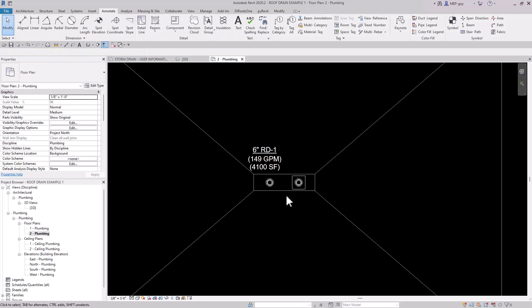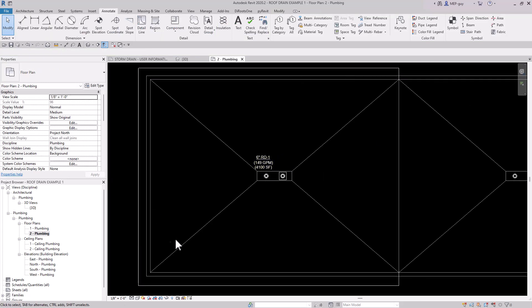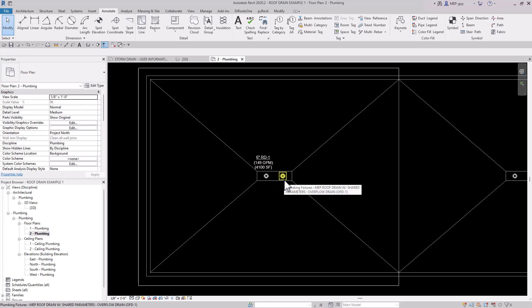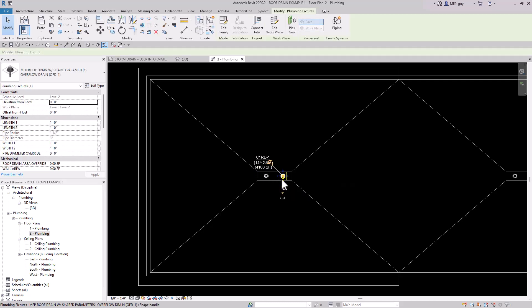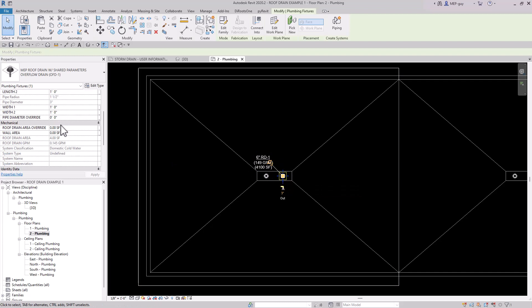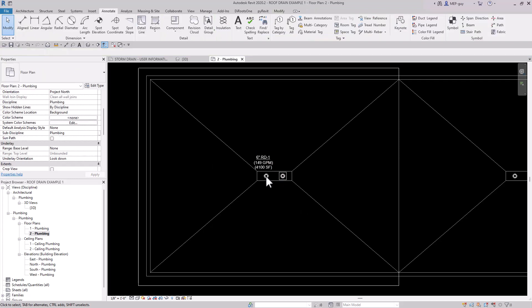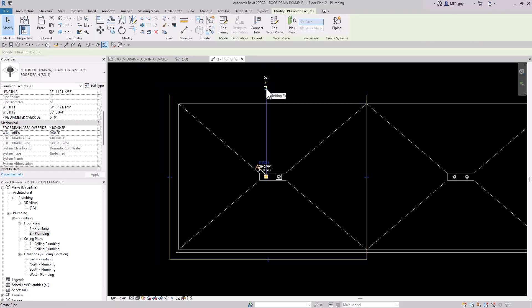Since we've calculated the size of this roof portion, we can use the same value for the overflow drain. I'll click the overflow drain, go to Roof Drain Override, type 4100, hit Enter — it automatically calculates the GPM. Now I'll click on the roof drain and click the pipe button, which automatically calculated that a six-inch pipe is needed based on the roof area. I'll draw the storm system pipe at negative three feet elevation, going 45 degrees.